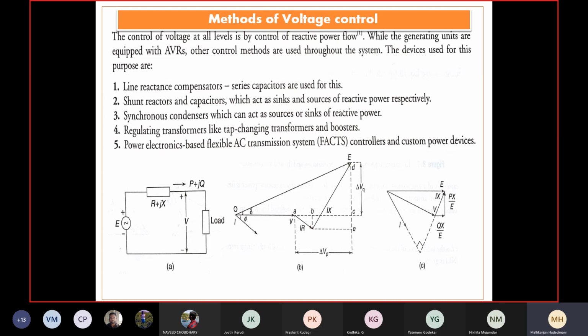The other way is a shunt reactor and capacitors, which act as a sink or source of reactive power respectively. This can be viewed from the perspective of loads, when a large industry or a huge connected capacity load is absorbing highly inductive power, highly lagging in power factor. Locally, a lot of capacitors can be hooked across the load terminals at different points, so that the lagging VAR can be compensated locally by the capacitor providing leading volt amperes. By adopting this load side compensation, you are meeting the requirement of reactive power locally, because it is very economic to compensate the reactive power at the point of need itself, as we are aware.